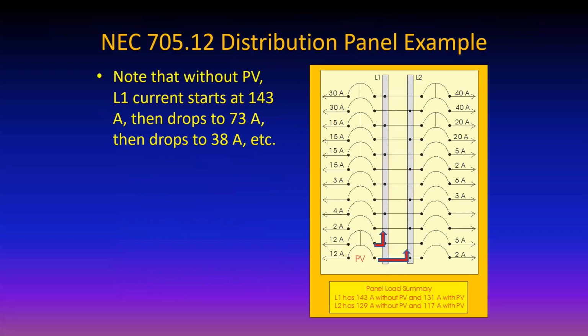Here's an example. You notice down at the bottom, we're feeding the bus bars from the bottom with 12 amps from the PV system, kind of a small system. But it also shows the loads on the bus bars. So without the PV, you're going to have 143 amps on line 1 and 129 amps on line 2. But as you're feeding backwards, you're making up 12 amps on each of those 2 lines. So that's 12 amps that doesn't have to come in on L1 and L2 from the utility. So you're actually doing a favor to your bus bars by tying that PV in at the bottom, because it reduces the load at the top by whatever amount of PV is coming in at the bottom.